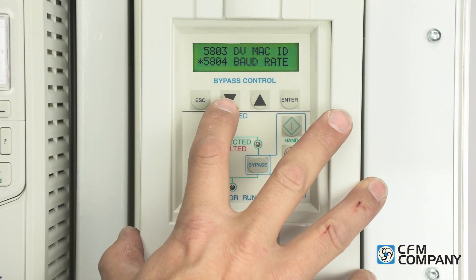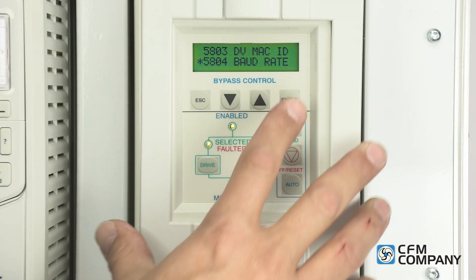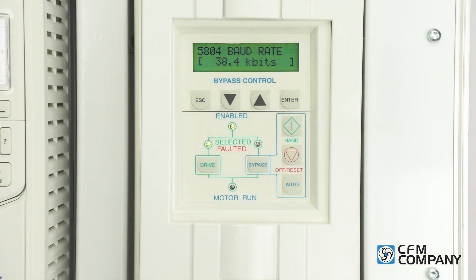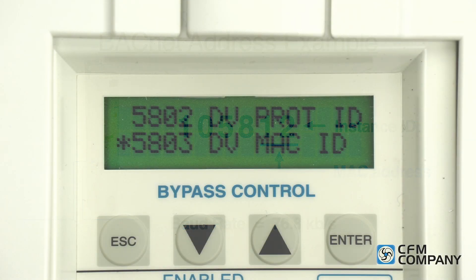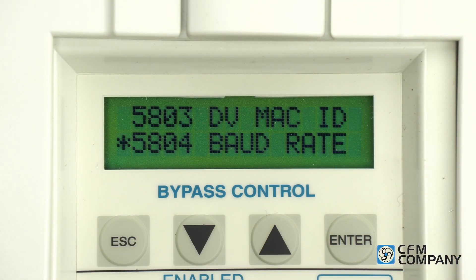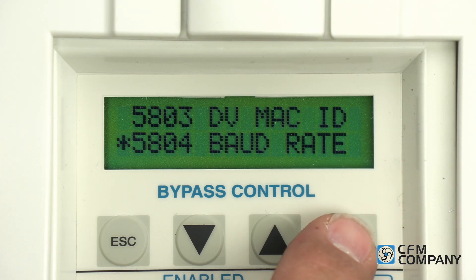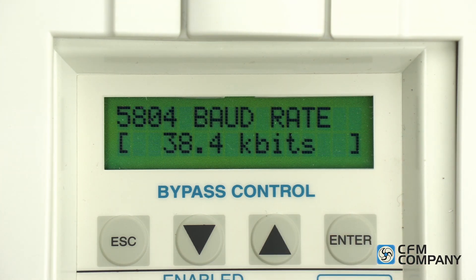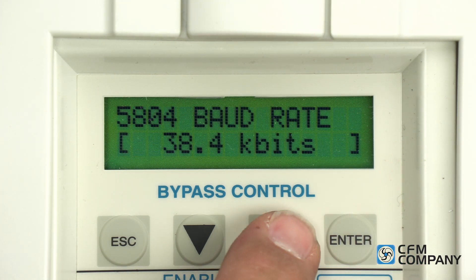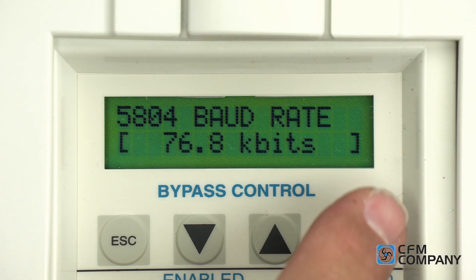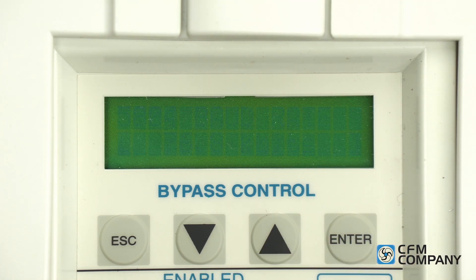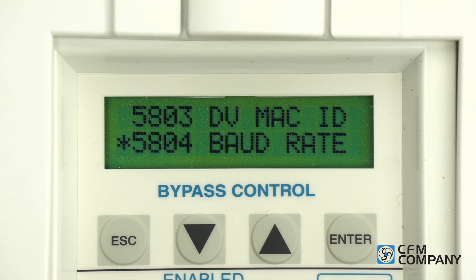Next is baud rate. The default is 38.4k. In our example, the baud rate is 76.8k. Press the down arrow to parameter 5804 baud rate and press enter to edit. Press the up arrow to change the value to 76.8k and press enter to save.